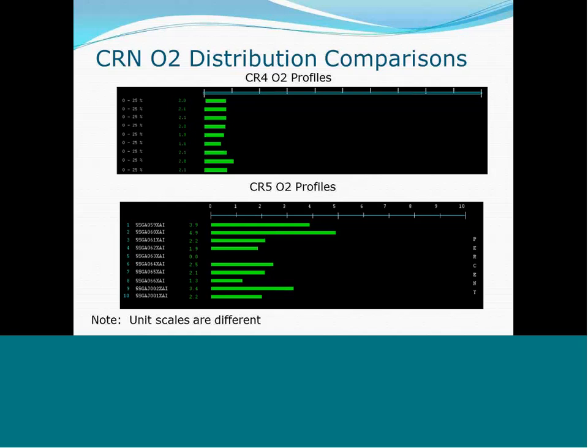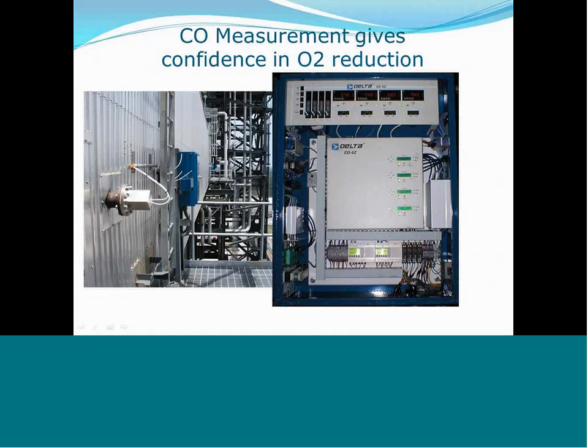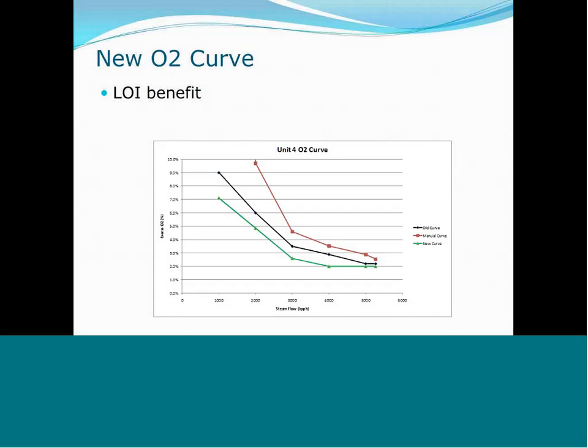Unit 5, subsequent to this paper, has also gotten a CCM, so its O2 grid will no longer look like that. Again, they measure CO on the back end with a separate CO probe and an infrared CO monitor, which is also capable of measuring O2 if they desire, and they did desire. So what did they do? This was their O2 curve before they added CCM, and this is their O2 curve after CCM was implemented.